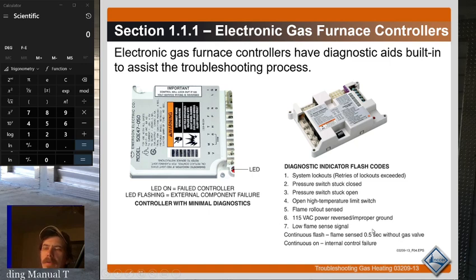It doesn't matter which one's hot and which one's neutral, okay? Most motors, if you hook up the wires opposite, it doesn't make a difference. It'll still run, and usually it'll run in the same direction. But there are certain boards that need to have the correct polarity, and furnaces are always one of them. Primarily, I believe, because of the flame sensor, because the flame sensor senses the signal through ground. That board has to be hooked up in the correct polarity or it won't work right.